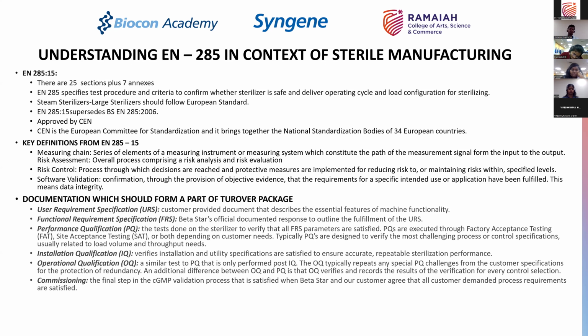The second part is data integrity, even in your software systems. If the instruments are not calibrated, they are not configured properly, or the automation sequence or the program is not written properly, you could have data gaps, as a result of which the data is not integral, and therefore you cannot have sufficient proof and evidence that your process is a sterile process. So software validation is a very important aspect of any modern day sterile manufacturing equipment.